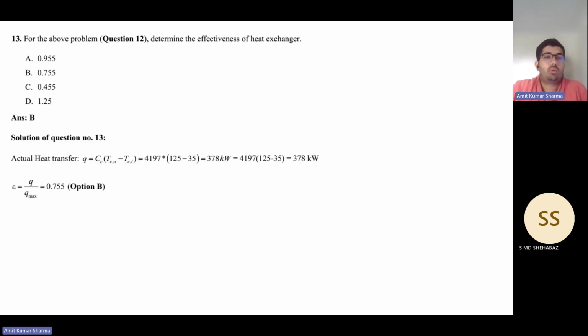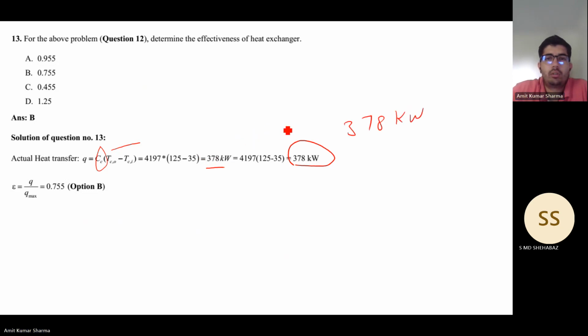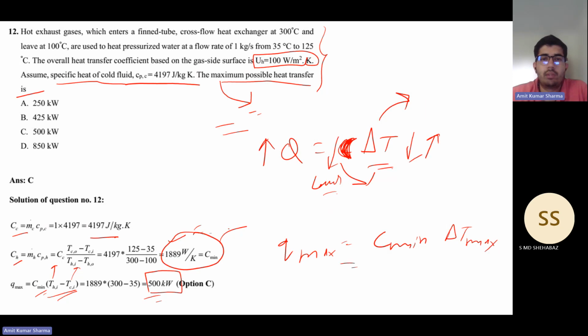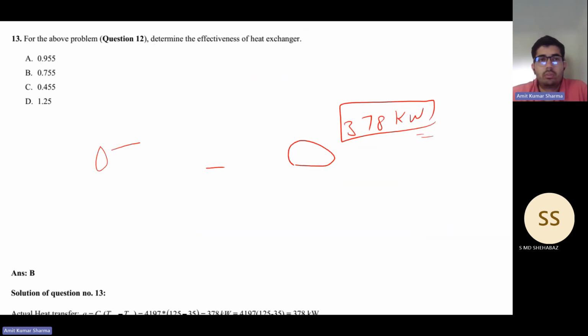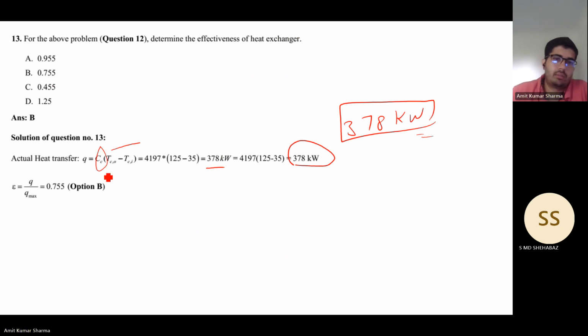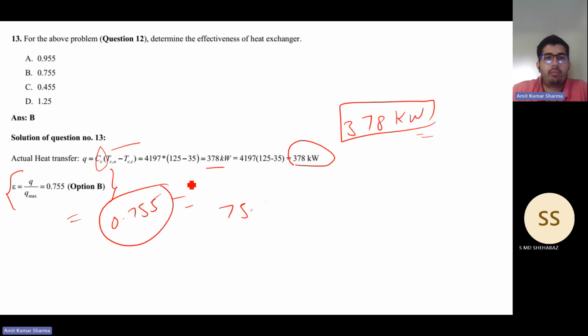Okay, so the solution is like this: the actual heat transfer would be using the cold capacity, and this is okay, so it's going to be 378 kilowatt. So the actual heat transfer is 378 kilowatt, but the maximum heat transfer that can be done, as we calculated, is 500 kilowatt. So the effectiveness is Q upon Q max, which comes to 0.755. So this heat exchanger is 75.5% effective.